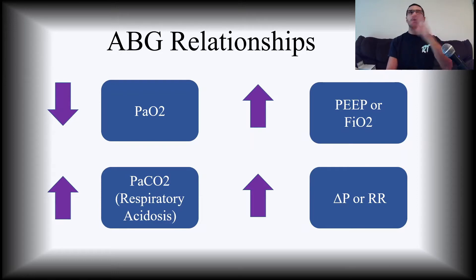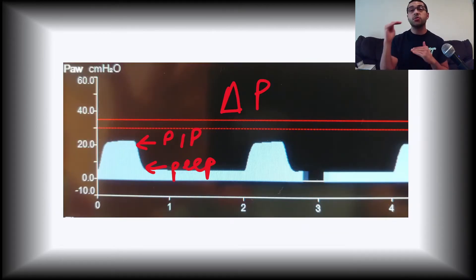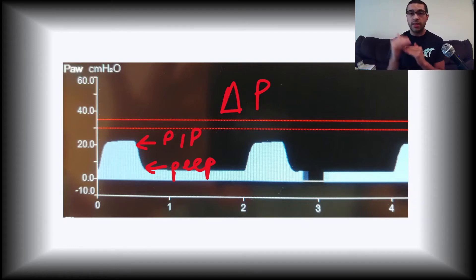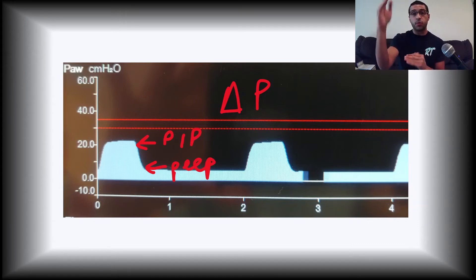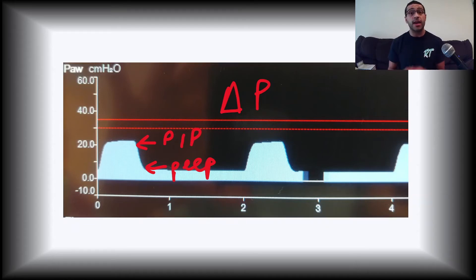Delta P — what do I mean by that? Isn't it just the PIP? Well, yes, you're not wrong, but I want to go into a little more about Delta P. Delta P is the change in pressure between the PIP and the PEEP — that difference is how much volume you're going to be moving. You can move the PIP up, which is the traditional way to do it about 90% of the time, or you can move the PEEP down, which is less used. But if you're in a tight spot where you've maxed out all of your options, that could be an option.